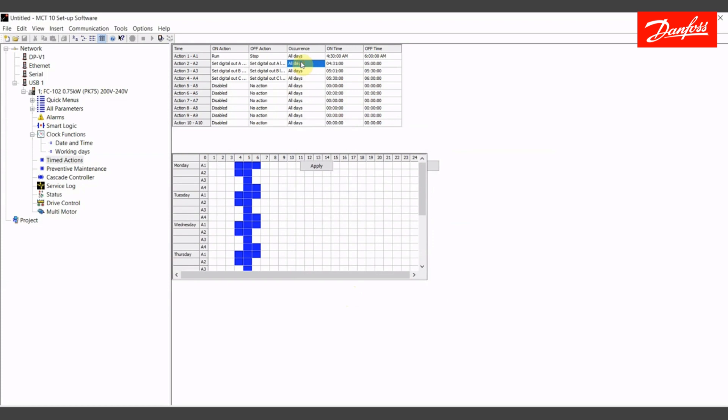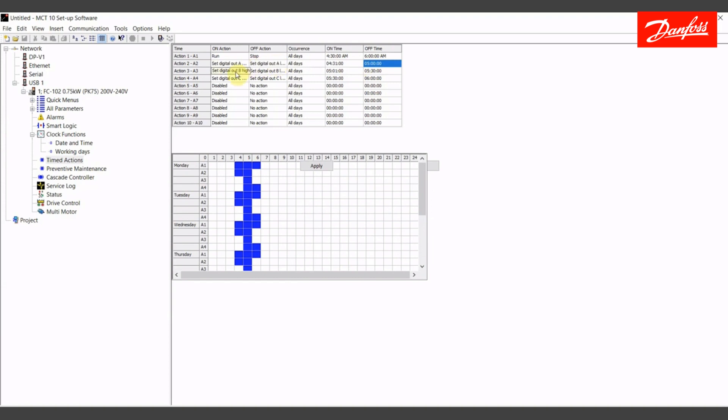The occurrence will be all days. This is going to happen from 4:31 a.m., so one minute after the drive starts in the morning. It'll take about a minute for it to get up to pressure, and then zone A will be energized and open. We'll run that until 5 o'clock a.m. So we have 29 minutes of runtime on that zone. The valve will shut off at this time because it's associated with my off action.